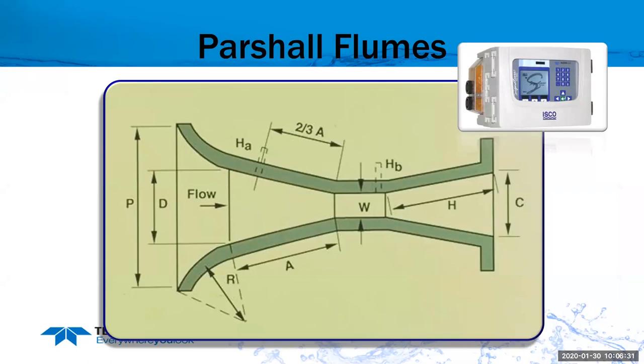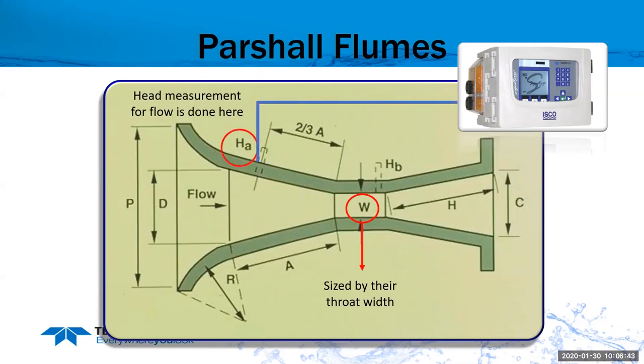So I have people call and ask what size flume I have. To determine that, you measure the width of the throat, and that will determine the size of your Parshall flume. Where you take your level measurement is H sub A, which is going to be 2/3 the length of that weir wall. You can reference the ISCO flow data handbook. They'll show you where that point is, or contact your manufacturer. When you order the flume, a lot of times they'll put a ruler or staff gauge at that location or make a mount for your sensor to make it easy to identify where to take your level measurement from.